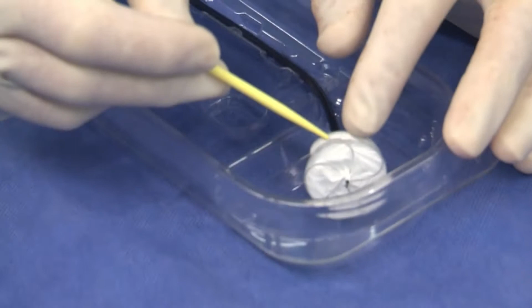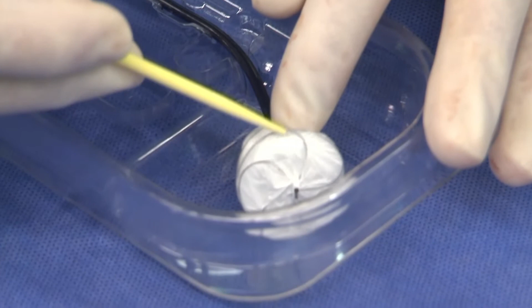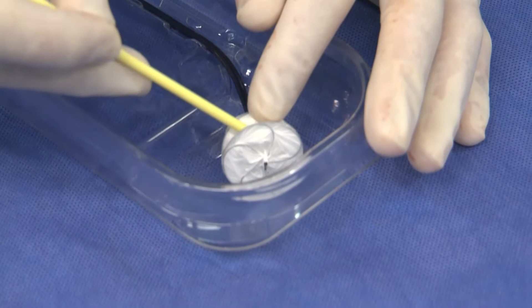So it's a double disc system just like the Helex, but the difference is that there are 5 wires in this frame rather than a single wire, which provides better coapting forces, and it brings the outer edges of the device into contact with the septum more completely. So early closure results tend to be better.